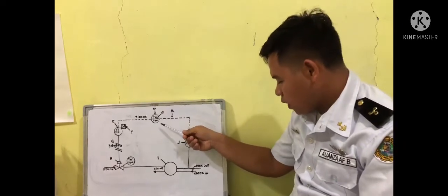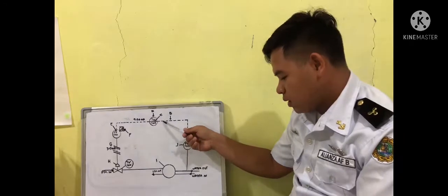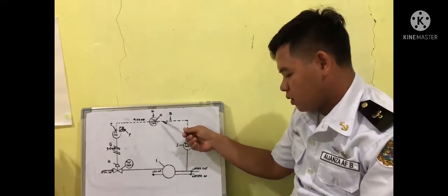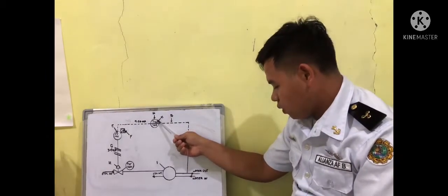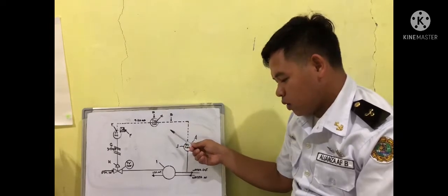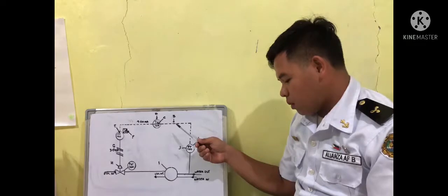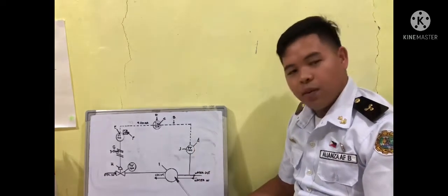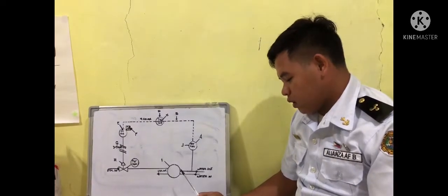The controller and indicator is the instrument where the transmitter sends the electrical signal, shown by the second letter, D, which symbolizes the temperature indicating controller. The role of the temperature controller is to measure the temperature on the thermocouple, compare it to the set point, and calculate the amount of time the heater should remain switched on to maintain a constant temperature.